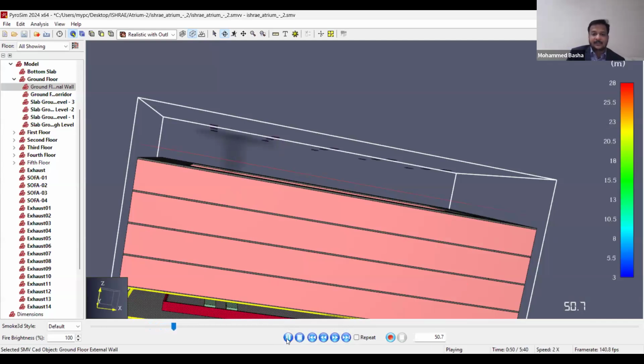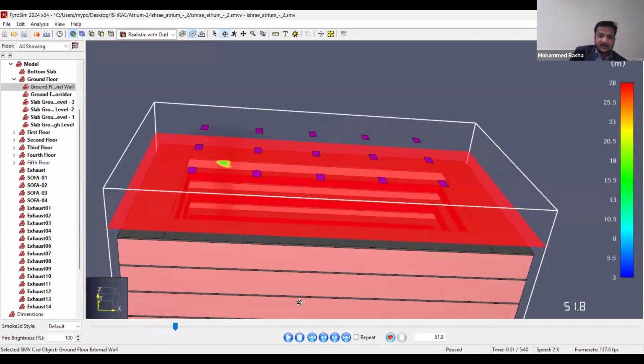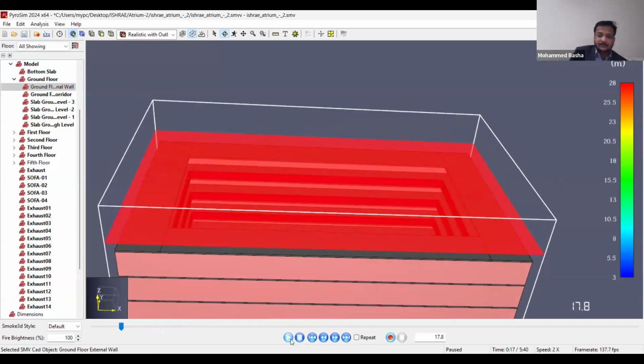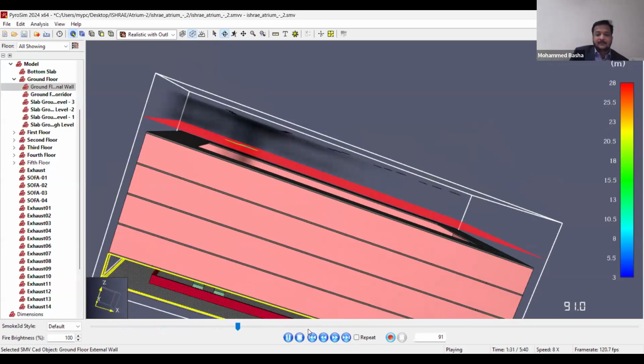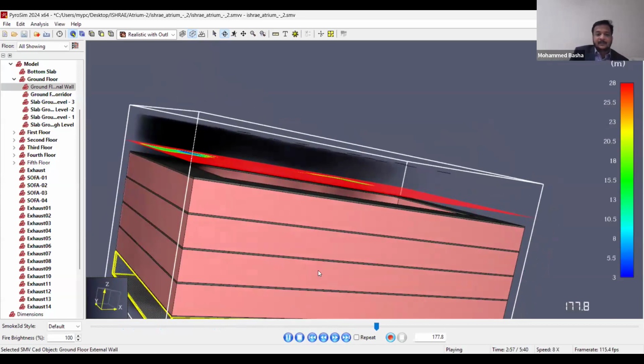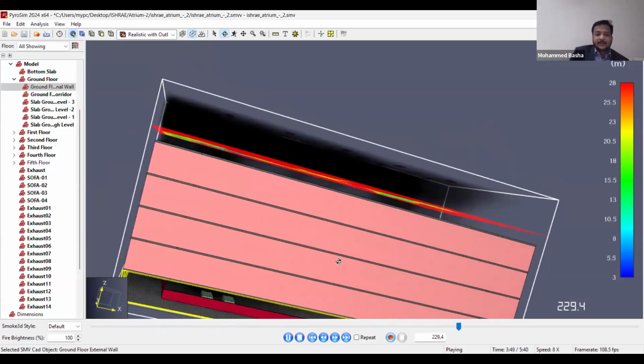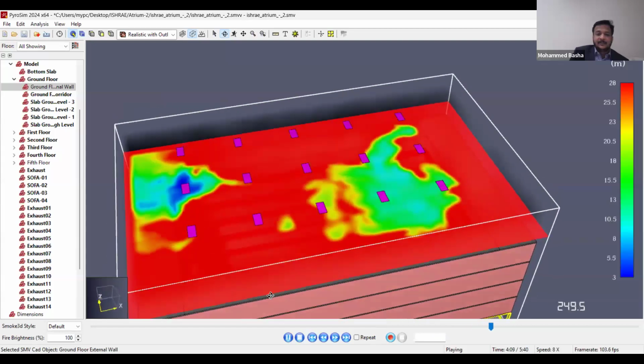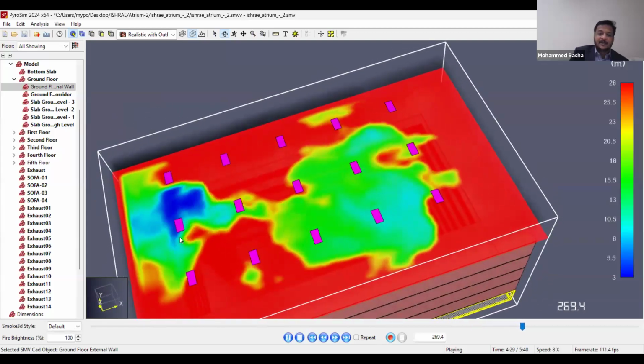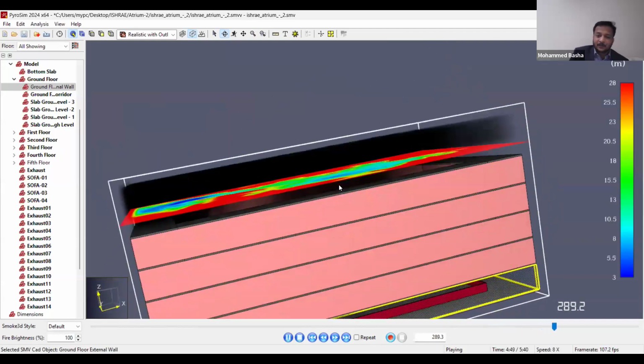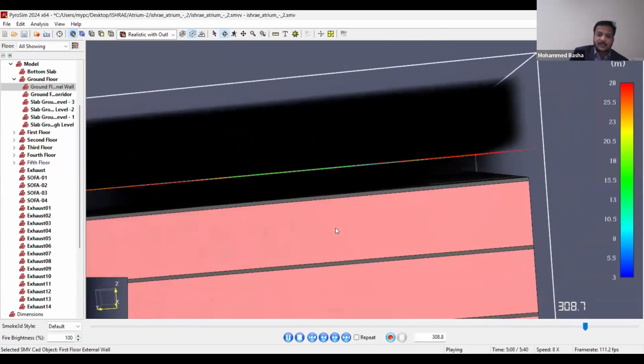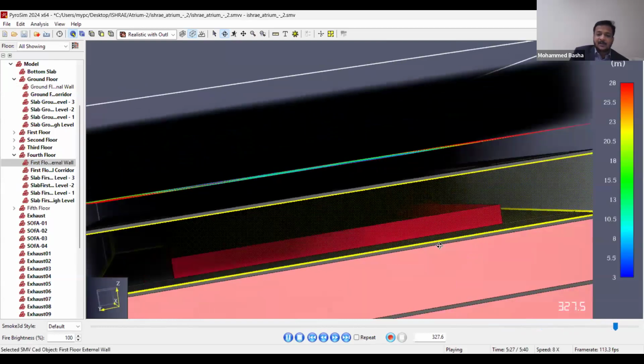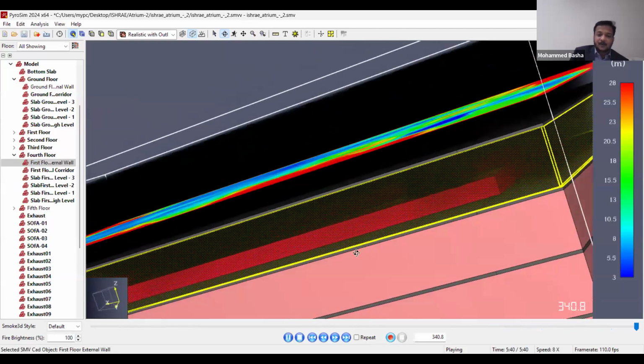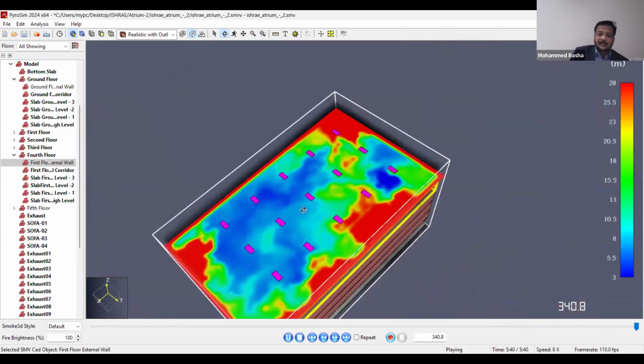Because this is the real scenario. We need to run by real scenario. You can see now, the exhausts are showing. But if you look here, you will not see. So let me run it fast. The smoke is coming. You can see the visibility. Okay, you have very clear visibility at 1.8 meters. You can see there is no smoke. The smoke you are seeing is at the middle, not at the walkways. Whereas you can check this here.